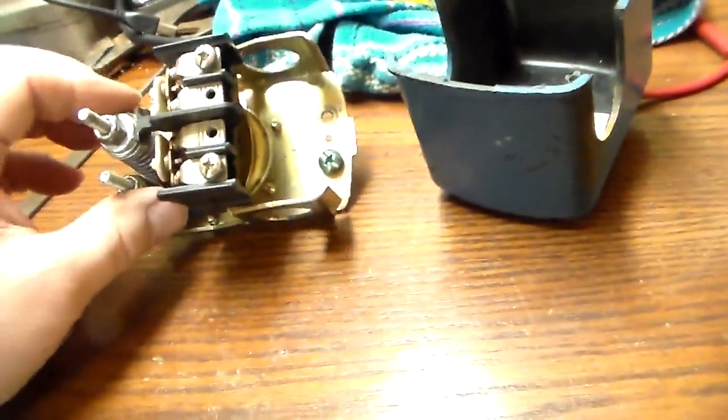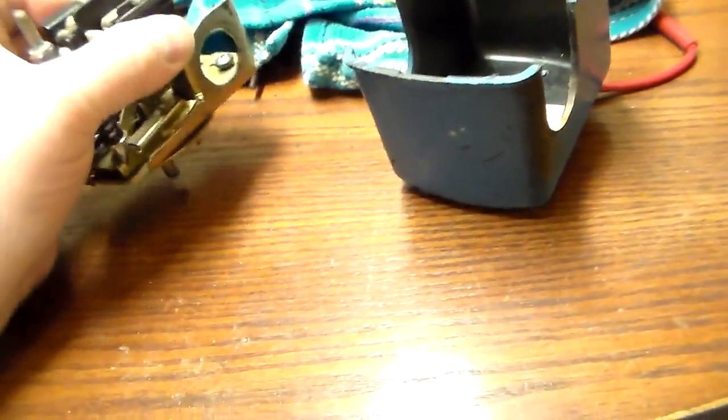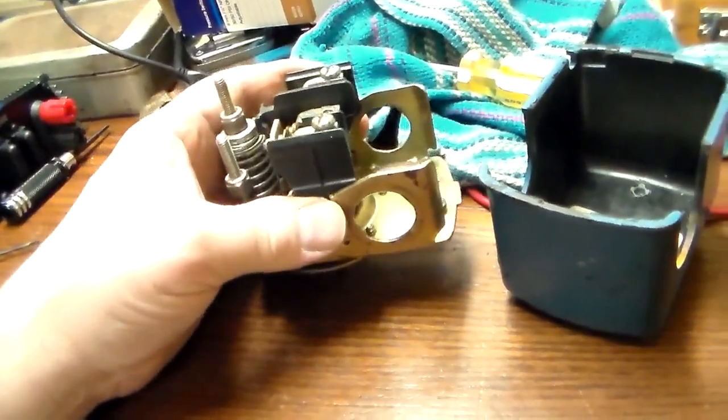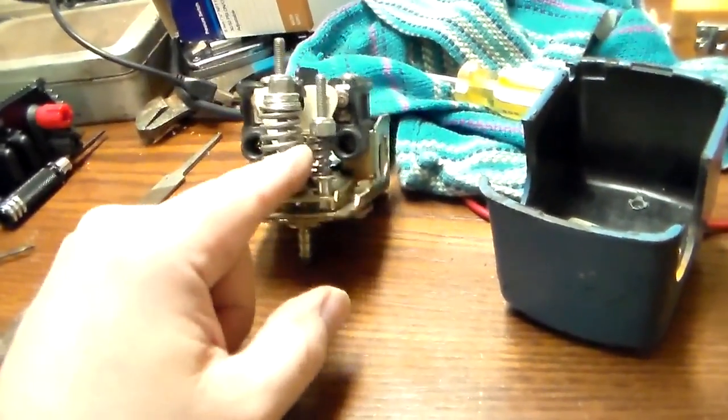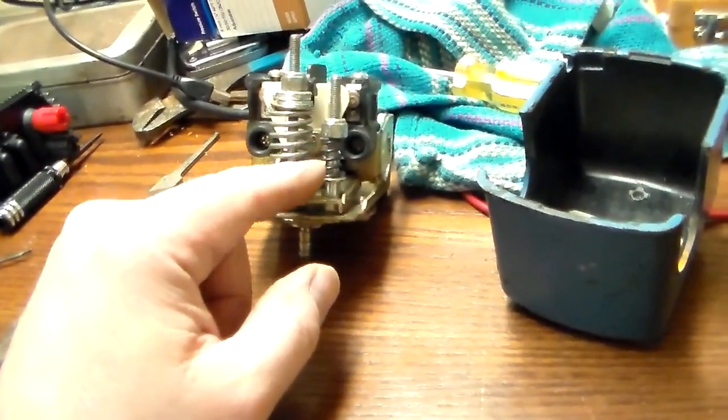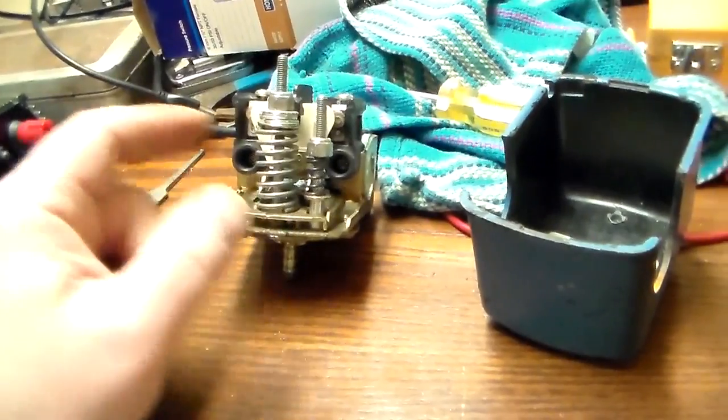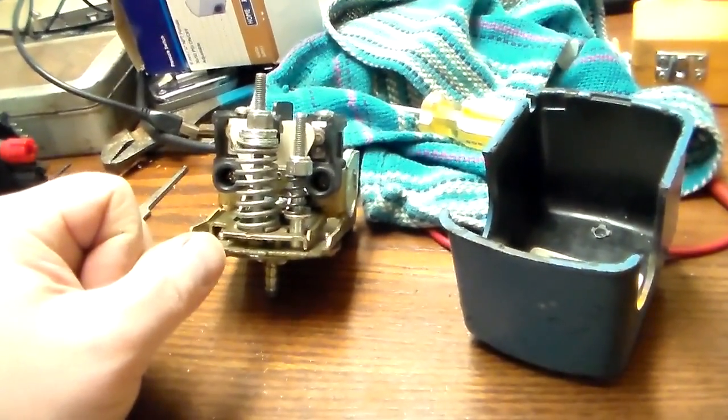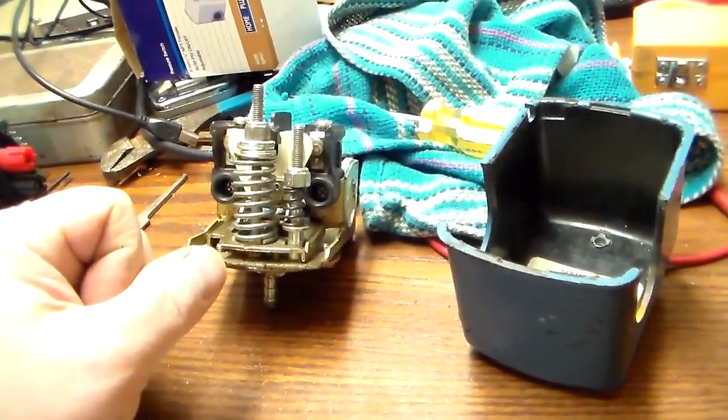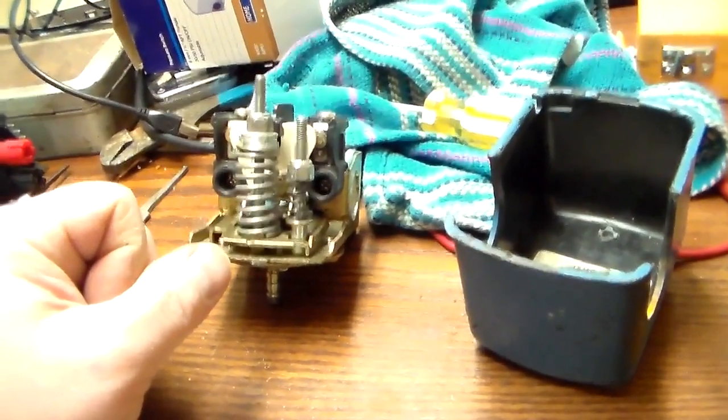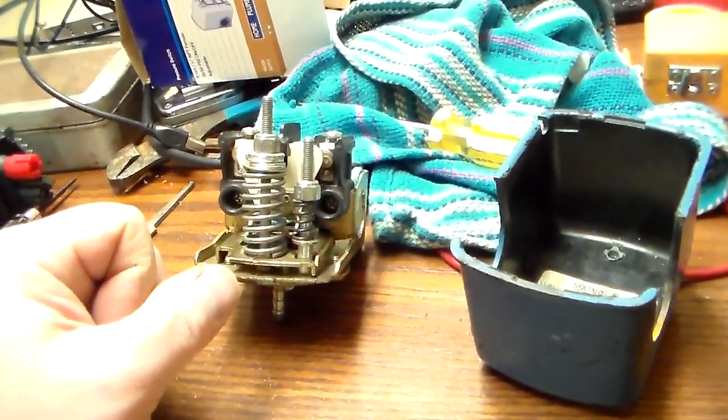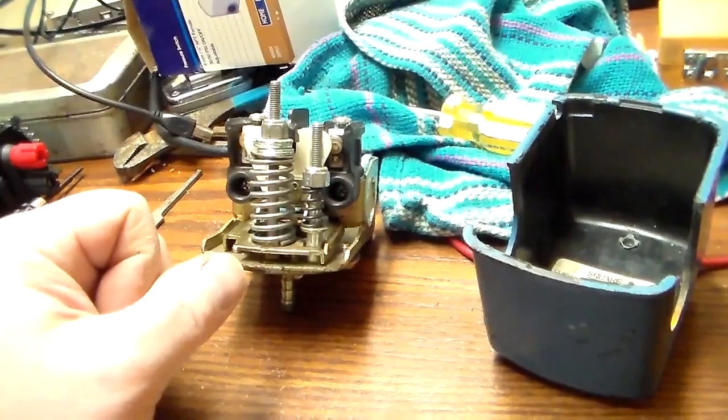I just cleaned out the crap that was in there so that's good enough. You may have to readjust your pressure settings. I'm on a half horsepower jet pump so I like mine at 30. This one here you can actually adjust both the cut in and the cut out, even though it's a little difficult. Some of them only have the one setting and the differential is already preset. But if I can get 10 psi difference I'm happy. Usually it's 20 psi difference. Like the last one I put in, I didn't touch it. It came already preset at 30 and 50, so it cuts in at 30 and cuts out at 50, which is standard for a jet pump.